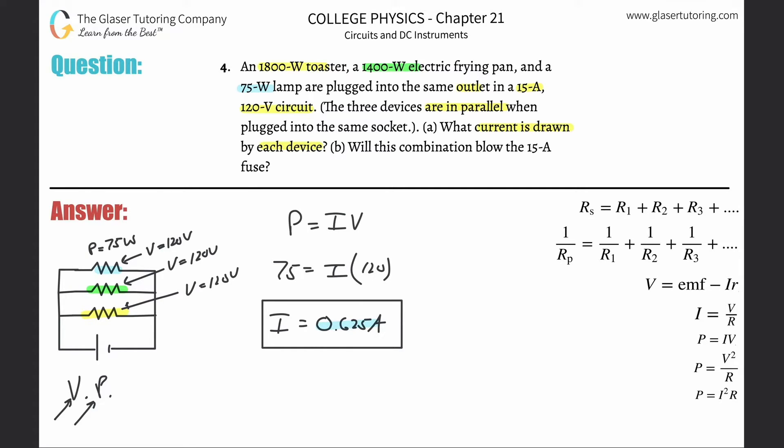That's the current flowing through that. I'm just going to rework this—I realize I'm going to use the same formula three times, which is just the power over the voltage. The power here for the green one is 1400, that's the frying pan, over the voltage of 120. That equals a current of 1400 over 120, which is 11.7 amps.